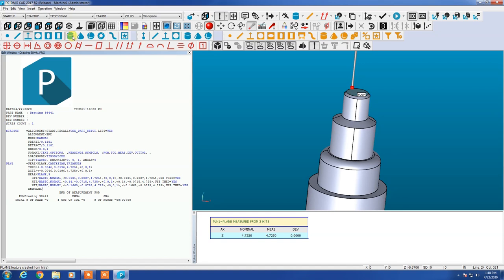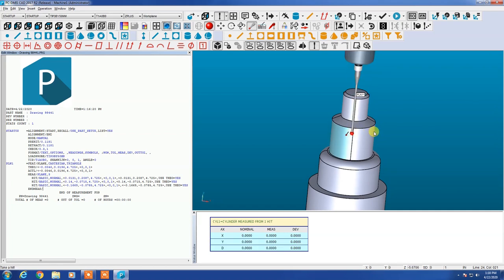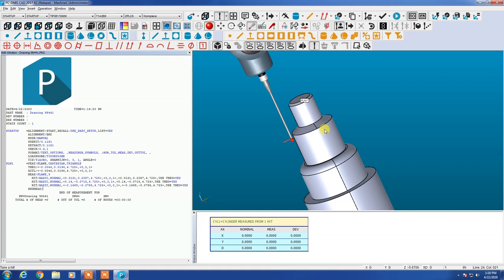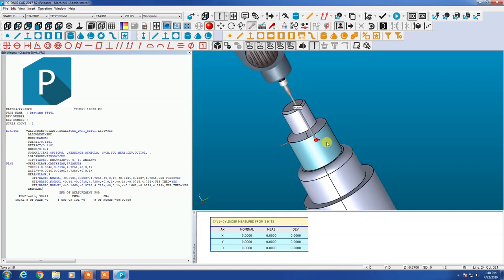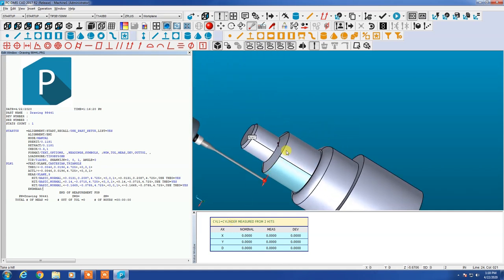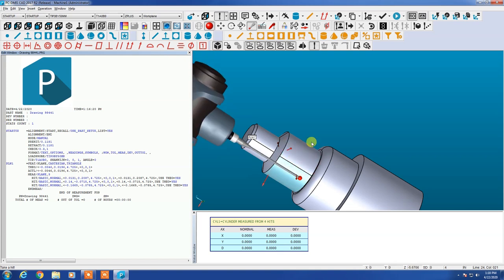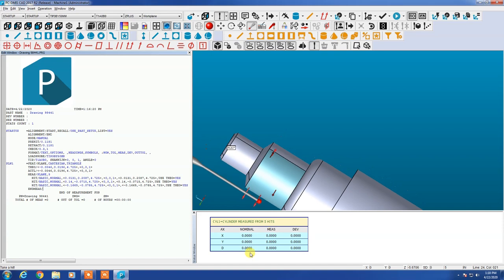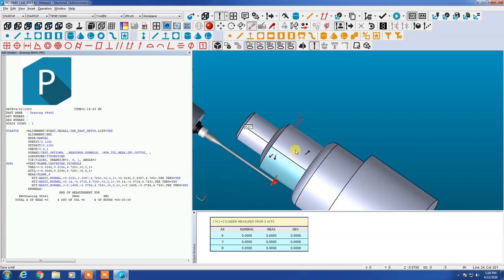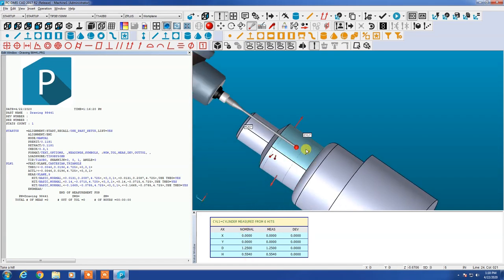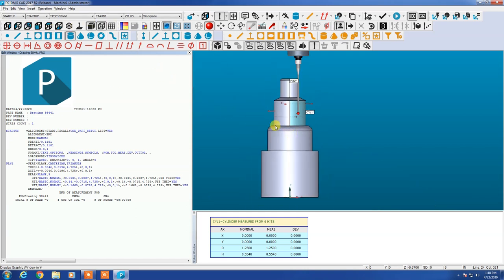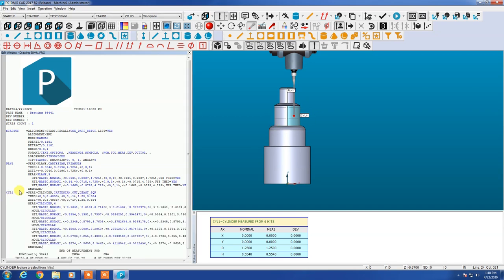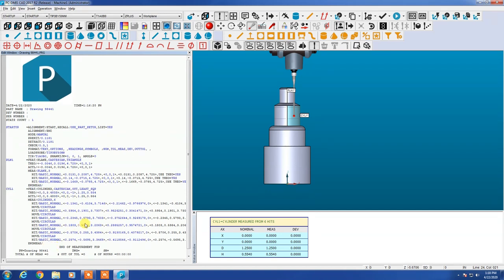Next we're going to look at that cylinder. So we're going to pick measured cylinder. We're still in program mode. We're going to place three hits around this cylinder on the same plane or very close to the same plane. So I'm attempting to place three pretty close and then three other hits minimum at random points around the cylinder. So those are six hits. I press the end button again and that will store our cylinder there as code. You can see we have cylinder one listed there and we show our six hits there. So those are the two features that we're going to use to create our alignment.